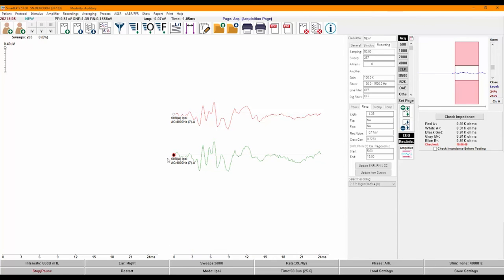When you have a recording selected and it is green, as you move along the recording, you'll be able to see where you are in time on the top of the screen. I will label the peaks as we did before while the recording is in progress. You can also adjust the placement of any peaks at any time — simply click on the label, it will become red, and then you can move the latency and amplitude markers as needed.